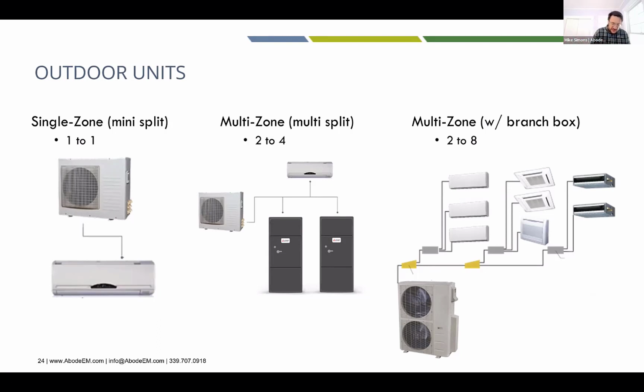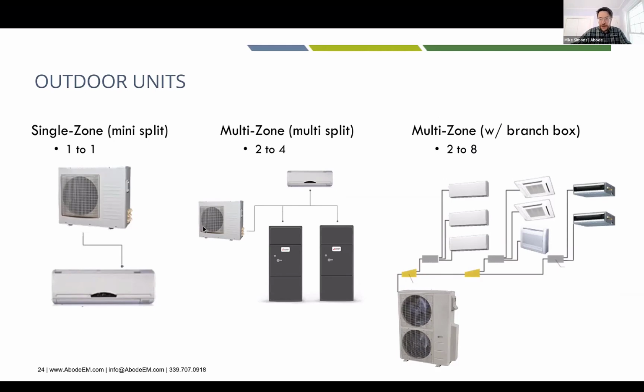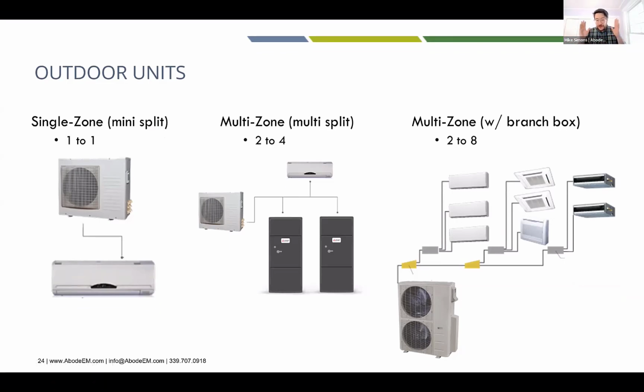And just to kind of gut check this as well, so we don't use rules of thumb with sizing heat pump equipment, but just if it's helpful to get an idea of this, most homes in Massachusetts probably need somewhere around like 25-ish BTUs per square foot. So say if a house is 2,000 square feet, they're going to need 50,000 BTUs worth of like heating capacity. So with knowing that, say, some homes need 50,000 BTUs worth of heating capacity, a 6,000 BTU system is where the mini of ductless mini split comes from. It's just picking up a small bit of the load.